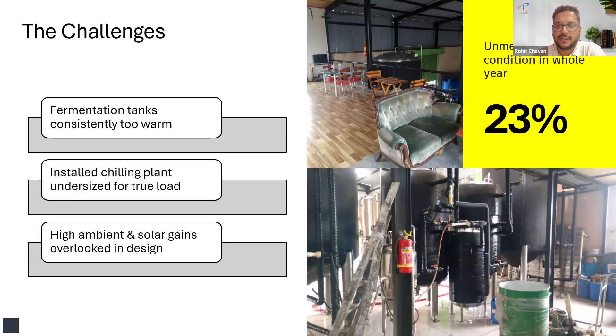What we did is create a virtual twin using the Buildings AI platform. We modeled everything as per the facility details, created the HVAC system, all the chillers, pumps, tanks, and tracked critical variables like chilled water temperature, pump flow, and chiller kW. Finally, we were able to visualize the current operational scenario in Tandem and see the hidden drivers. What was revealing is that ambient heat and solar gains were really underestimated, even though the design was created as per the handbook.